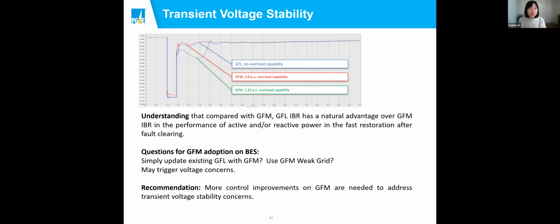The other thing I want to say is, I didn't test it, but obviously there are a lot of tests proving that grid forming inverters will be more stable in a weak grid than grid following. However, I still want to caveat that in a weak grid, although the grid forming inverter can be stable and controlled as expected in performance, if you are expecting this kind of performance that gives you a voltage dip post-contingency, and weak grids tend to have even worse voltage recovery, and the voltage is more sensitive to reactive compensation, then you may also end up with a voltage stability concern in the weak grid with the performance like this on the green chart. So these are the things I think we need to further think about before we adopt grid forming inverters for local voltage issues.